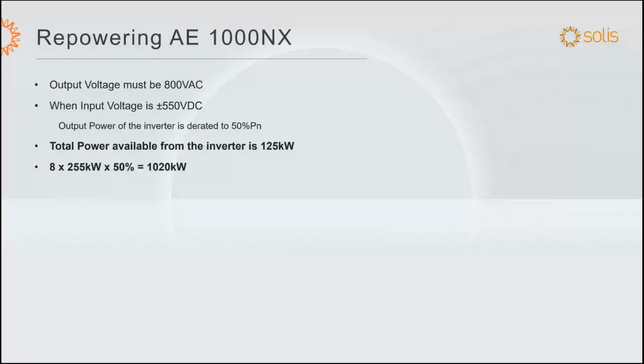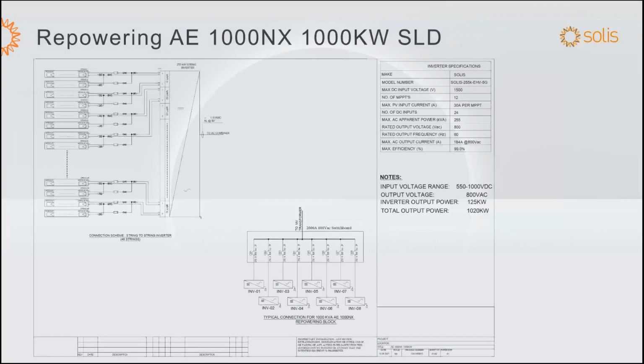The main reason for that derating is the low input voltage range. At the DC voltage of 550, the inverter will have to be derated to 50% of its nominal power. Therefore, it will be about 125 kilowatt based on that. The design is similar there. This design has 12 MPPT, and we can accommodate 48 strings. So that could replace pretty much any combiner box that was used with this inverter. And then we will need to connect 8 inverters to the AC switchgear. Each inverter will have its own circuit breaker, basically a combined switchgear to the medium voltage transformer. And this is an 800 volt installation.